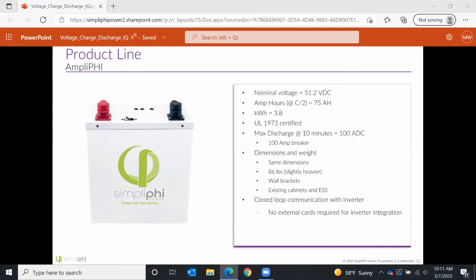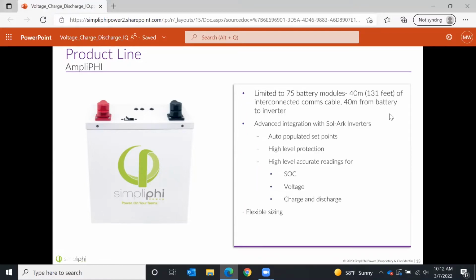Now, the advantages here are, first off, the communications is going to allow your customer to see a high level of accuracy in terms of state of charge, voltage, as well as charge and discharge amperage at any time. I find customers are almost always wanting a battery monitor installed with their products. So this eliminates the need for that battery monitor as it's internal to the BMS. It's going to show the state of charge through the Sol-Ark's LCD screen, or the same with the Sunny Island, as well as their respective online monitoring platforms like PowerView.